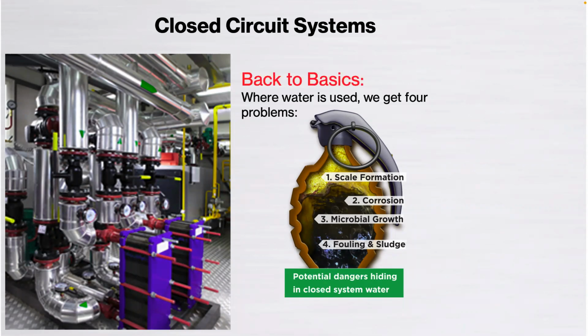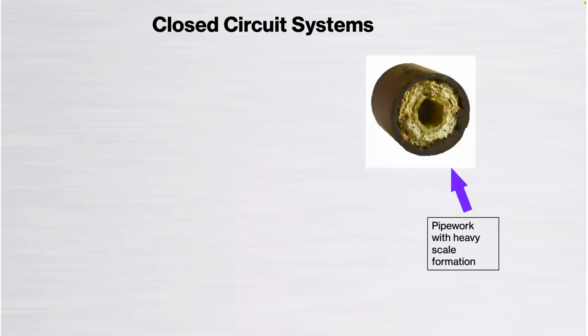We have microbiological growth, something I think the industry is going to see more and more of, and again hone in on, because of the operating temperatures of a lot of new technologies, the higher efficiency systems, and certainly heat pump systems, etc., that run at much lower temperatures. We're going to see more issues with bacteria if it's not addressed. And then fouling and sludge, which is essentially all of the above. There could also be contamination from construction debris as well.